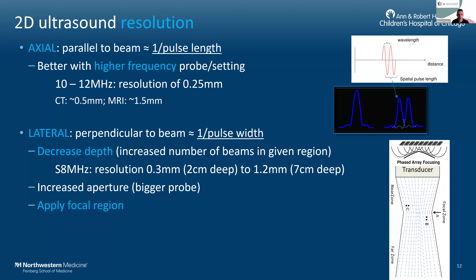So the pulse width is narrower closer to the probe before these lines spread out. And additionally, using a focal zone can narrow the pulse width at a zone of interest. This is accomplished by the probe timing or steering the pulses that are emitted from the probe to intersect the scan lines at a particular depth. And we can actually set this on the echo cart. And in general, the focal zone should be placed at or just slightly beyond the area of interest.